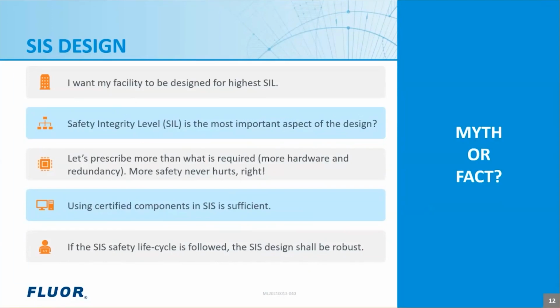Thanks for setting up the context, Veronica. Yes, definitely. There are still a lot of misconceptions around SIS and SIL. The functional safety standards, such as IEC 61508 and IEC 61511, are good guides for designing SIS. But understanding these in detail and a holistic implementation strategy involving all key stakeholders is necessary. Each stakeholder, like end user, engineering consultant, EPC contractor, SIS and instrumentation vendors, leaves their mark in the design or operation of the SIS. How well the functional safety requirements are understood and implemented will decide the success of the process safeguarding mission.